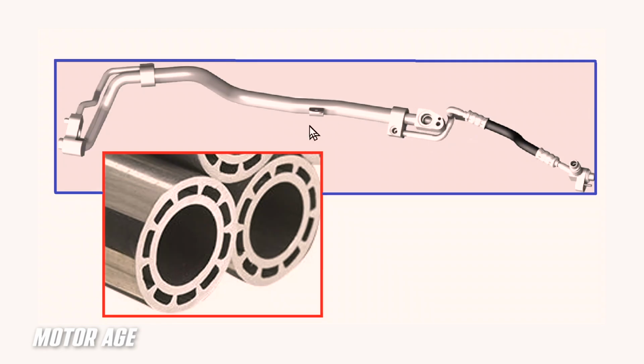But these two Siamese pipes are impregnated within one another. And if you were to cut one apart, it would look something like this. You'd have the low side portion of the hose on the inside and the high side portion of the hose on the outside. Now, what's the purpose of us doing this? It's two different processes, one known as superheat and the other one known as subcooling. So let's talk about that for a moment.